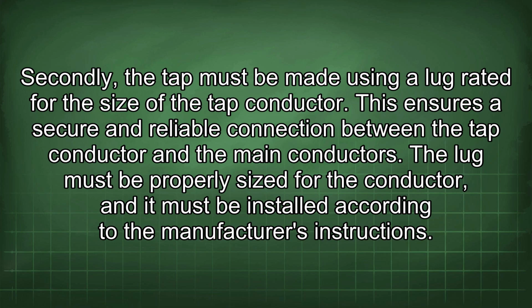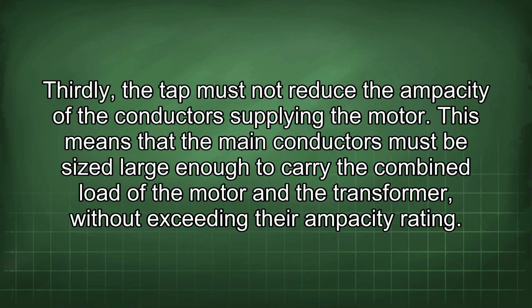Secondly, the tap must be made using a lug rated for the size of the tap conductor. This ensures a secure and reliable connection between the tap conductor and the main conductors. The lug must be properly sized for the conductor, and it must be installed according to the manufacturer's instructions. Thirdly, the tap must not reduce the ampacity of the conductors supplying the motor.